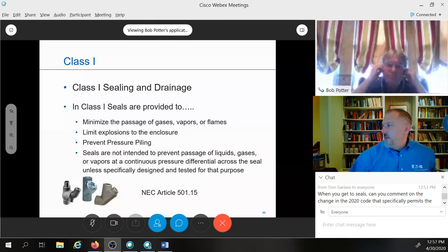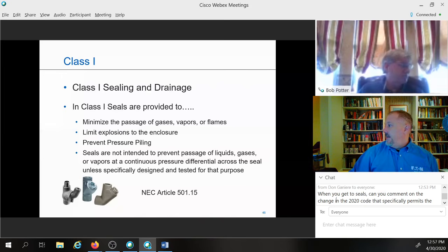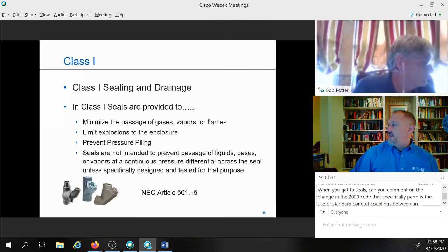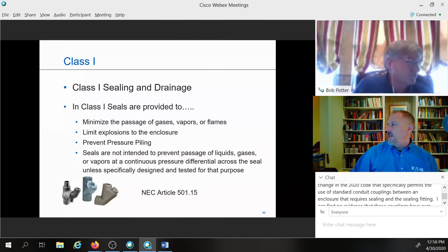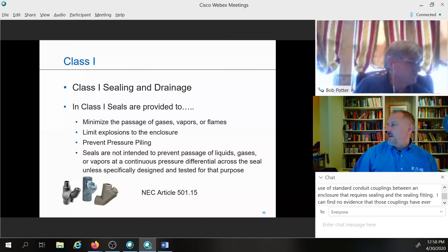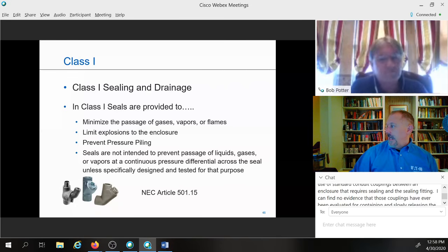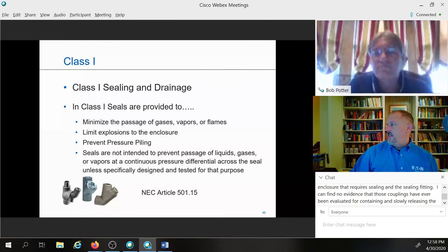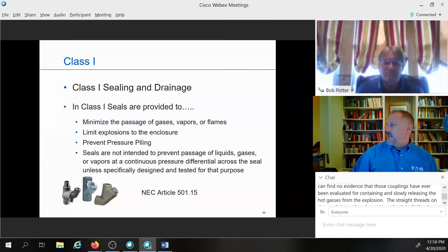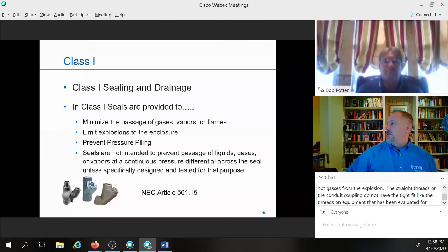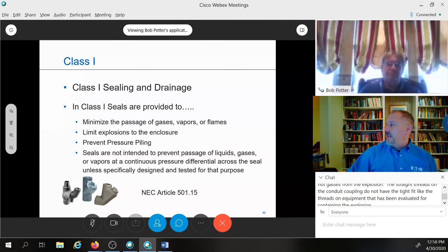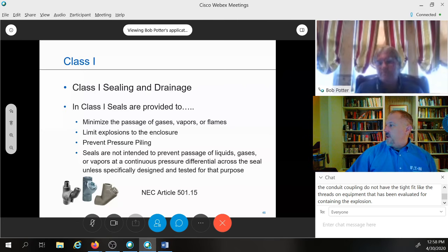Okay, I got another one here from Don Gannier. When you get to seals, I'm not sure if you're there yet, but he says, can you comment on the change in the 2020 code that specifically permits the use of standard conduit couplings between an enclosure that requires sealing and the sealing fitting? He says he can find no evidence that those couplings have ever been evaluated for containing and slowly releasing the hot gases from the explosion. The straight threads on the conduit coupling do not have the tight fit like the threads on equipment that has been evaluated for containing the explosion. Can you comment on that one?